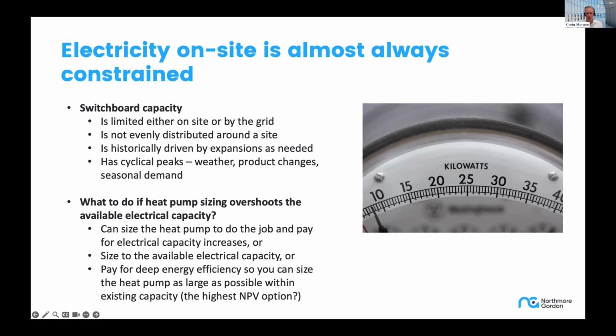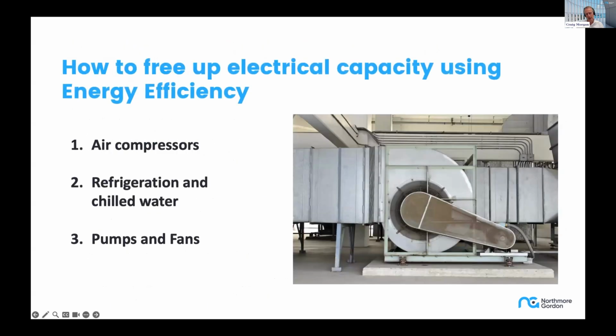So what do you do if an electrification exercise, or in this case a heat pump, overshoots the available electrical capacity? You could size the heat pump to do the job and pay for the electrical upgrade, or size it to the available electrical capacity — partial electrification is a pathway we recommend for some customers. Or you can use the avoided upgrade money to go deeper on energy efficiency, which lets you size the electrification project as large as possible. Since you're also getting energy savings, it's probably the highest NPV option.